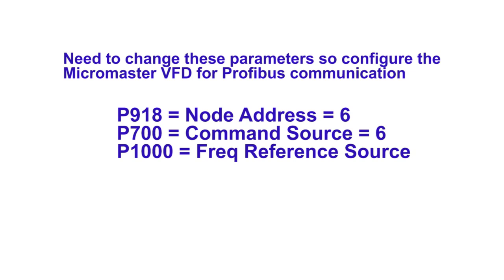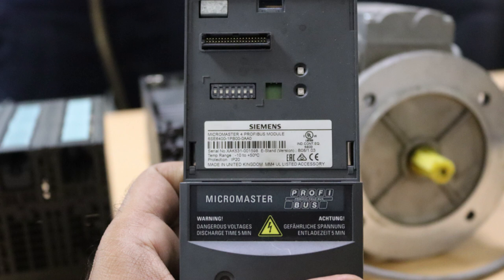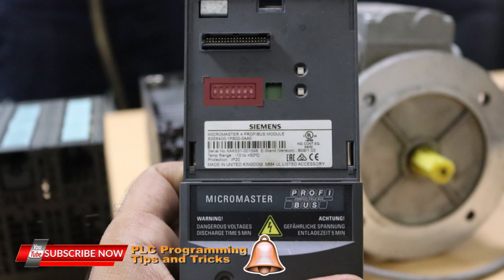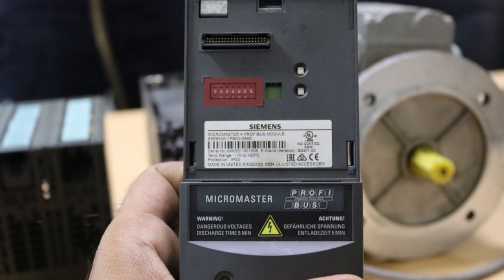The third parameter is P1000 and it is the reference frequency. Now as you can see, this is our Profibus module and on the top there are DIP switches used to configure its node address. Remember: if all DIP switches are set off, the VFD will not read these DIP switches and will directly take the address from parameter P918, which we have set to 6. If we set the node address from the DIP switches, then parameter P918 will be bypassed and the VFD will read the node address directly from the DIP switches. These are the initial settings before starting programming in Simatic Manager.